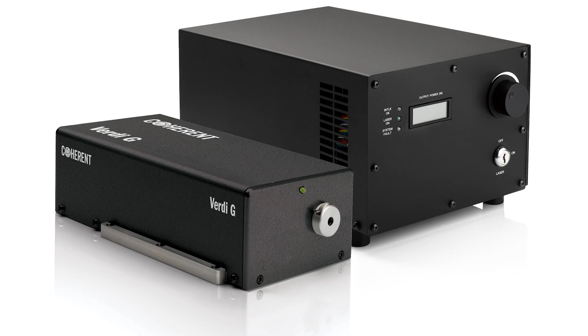A Class 3B laser is hazardous if the eye is exposed directly, but diffuse reflections from matte surfaces are not harmful. The accessible emission limit, AEL, for continuous lasers in the wavelength range from 315 nanometers to far infrared is 0.5 watts. For pulse lasers between 400 and 700 nanometers, the limit is 30 millijoules. Other limits apply to other wavelengths and to ultrashort pulse lasers. Protective eyewear is typically required where direct viewing of a Class 3B laser beam may occur. Class 3B lasers must be equipped with a key switch and a safety interlock.